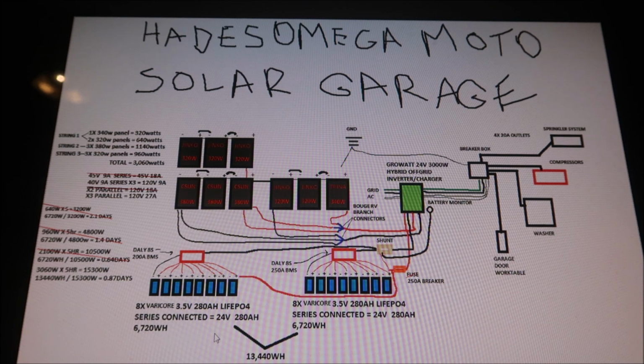Then you add those two together. So you have another one, and you have it in parallel. You've got a series here, another series here, and then you put them in parallel, so you've got a series parallel setup. When you do that, it increases the capacity but not the voltage. So our total capacity is 13.44 kilowatt hours, or 13,440 watt hours.